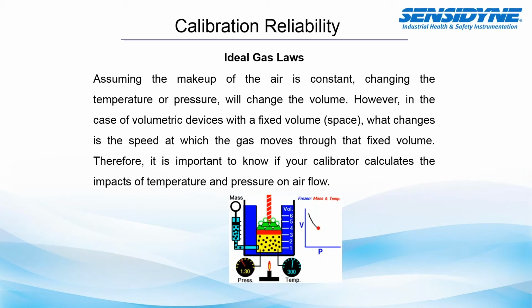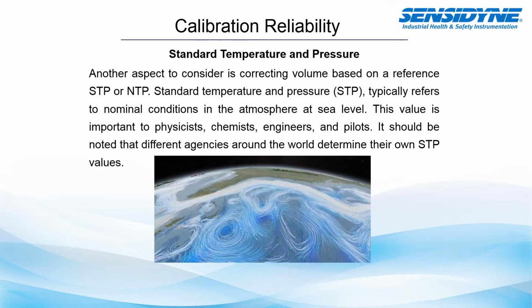Some of the older calibrators on the market do not. However, several of the newer calibrators will actually have formulas to compensate for temperature and pressure as it relates to the speed at which the air moves through the calibrator and is measured. So another aspect to consider is correcting the volume based on a reference standard temperature and pressure, or a normalized temperature and pressure.